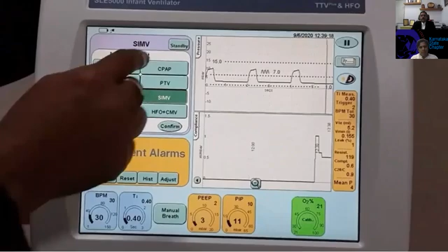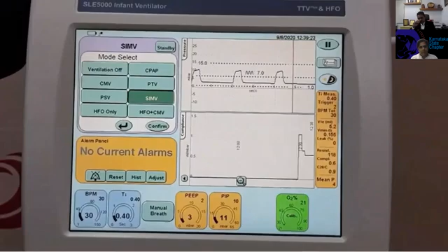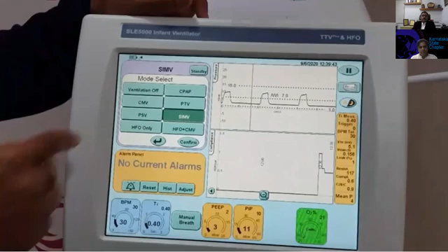Now this is another mode here called standby. This standby mode is especially useful when you are suctioning the baby, and more so when the baby is on a high frequency ventilator, because it avoids de-recruitment of the lung, and it becomes easier to continue with the ventilation after the suction. The other mode, ventilation off, is a mode which you can use to set the ventilation.